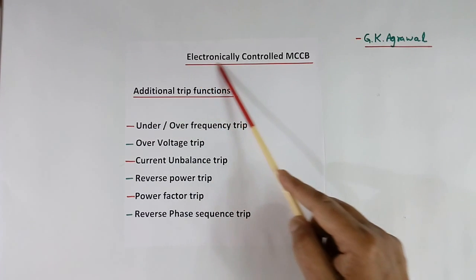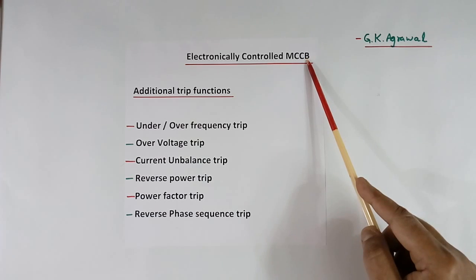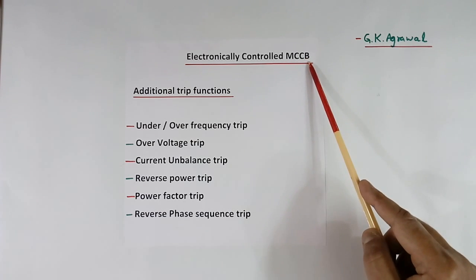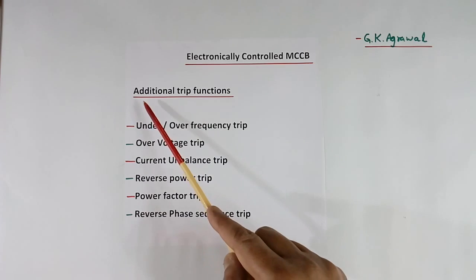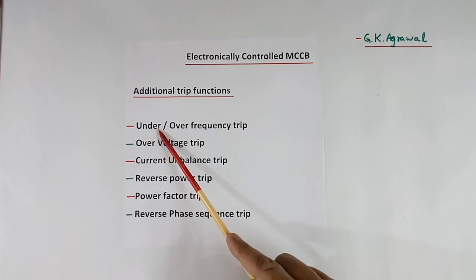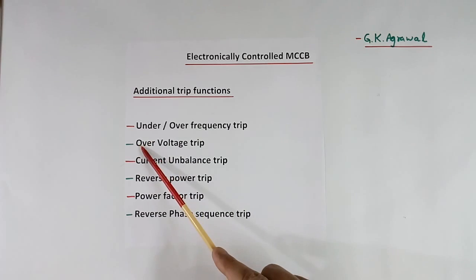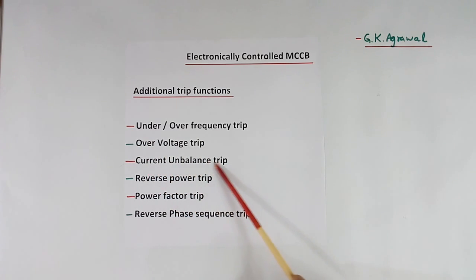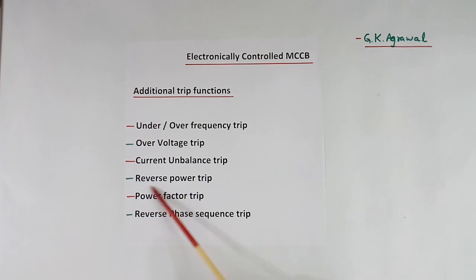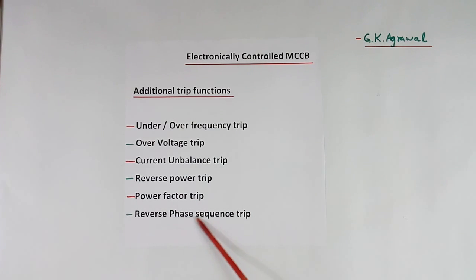Nowadays electronically controlled MCCBs are also available. In addition to the functions we have discussed, they have additional trip functions also, like under/over frequency trip, over voltage trip, current unbalance trip due to load unbalance, reverse power trip, power factor trip — if power factor comes down too much, then MCCB will trip — and reverse phase sequence trip.